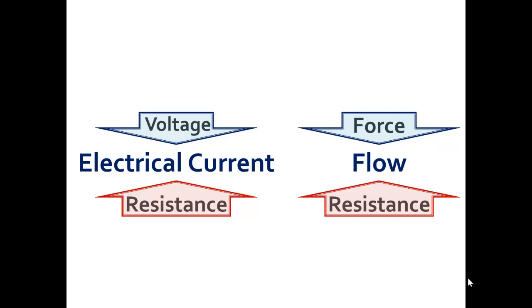So in an electrical system, a good example would be in a thunderstorm, if a bolt of lightning hits the power lines and sends a surge into your house, the plastic and rubber insulation on all of the conductors running through your home have a rating usually of 600 volts. If that voltage is exceeded, and they measure the ability of a material to insulate electrically, they call it dielectric strength.